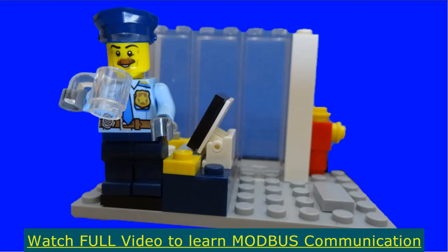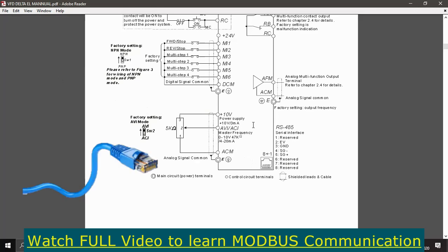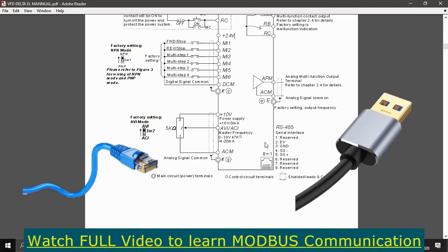First we will look at the hardware needed for communication between the VFD and the PC. You need the manual for your VFD — I have the Delta VFD EL manual. The concept for communication is the same regardless of manufacturer, so just have the proper manual PDF ready. From the VFD side I have an RS485 interface, and from the PC side I have USB, which is RS232. So I need an RS485 to RS232 converter.